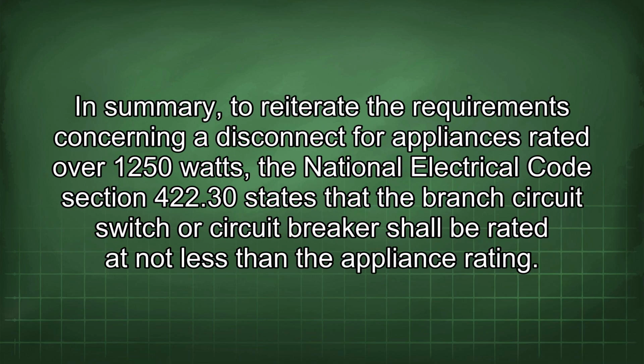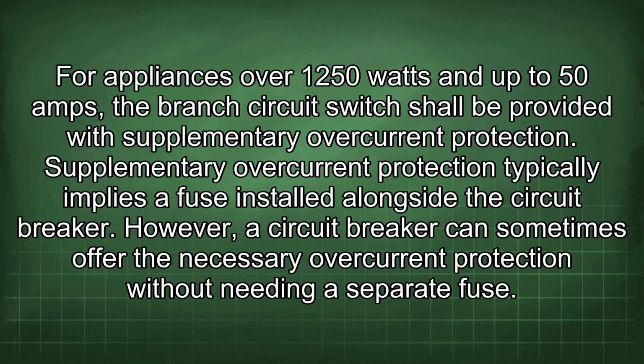In summary, to reiterate the requirements concerning a disconnect for appliances rated over 1250 watts, the National Electrical Code Section 422.30 states that the branch circuit switch or circuit breaker shall be rated at not less than the appliance rating. For appliances over 1250 watts and up to 50 amps, the branch circuit switch shall be provided with supplementary overcurrent protection. Supplementary overcurrent protection typically implies a fuse installed alongside the circuit breaker. However, a circuit breaker can sometimes offer the necessary overcurrent protection without needing a separate fuse.